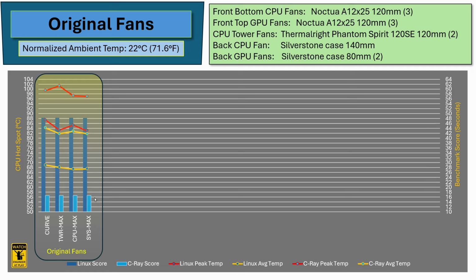Looking at this in general, I see a bit of a downward trend when the fans are constantly at maximum. There's a bit of margin of error, but I think it's safe to say that when more fans are set to run continuously at maximum, there is a slight improvement in the peak core temperatures.